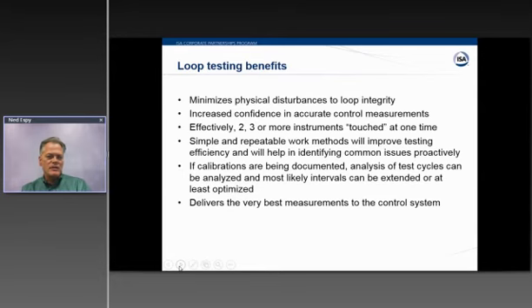And to kind of wrap this up, what are the benefits of doing loop testing? Well, it's really good that you're not breaking into the loop and disturbing all the different wiring connections and components. You could miswire things when you put it back together. You're going to have an increased confidence in your measurements when you're doing loop tests. There's going to be less arguments, less disagreements. With a loop test, as I mentioned, you're touching, in this case, 2 or 3 instruments in our example, all at one time. And you're not making unnecessary tests if the loop is checking out.